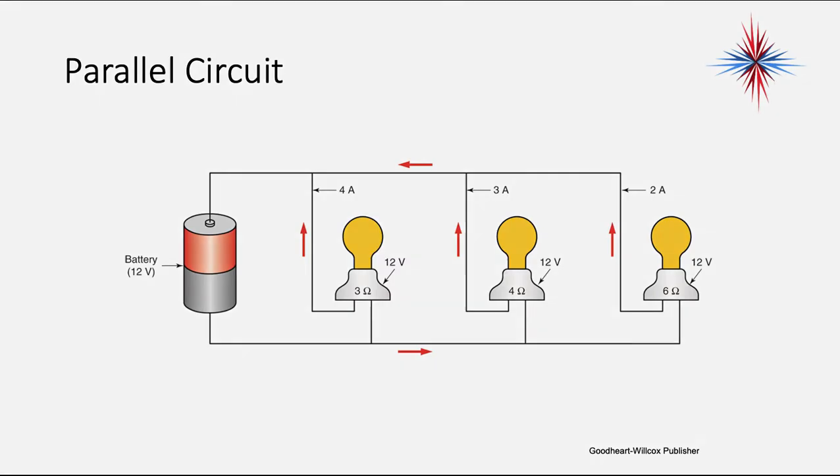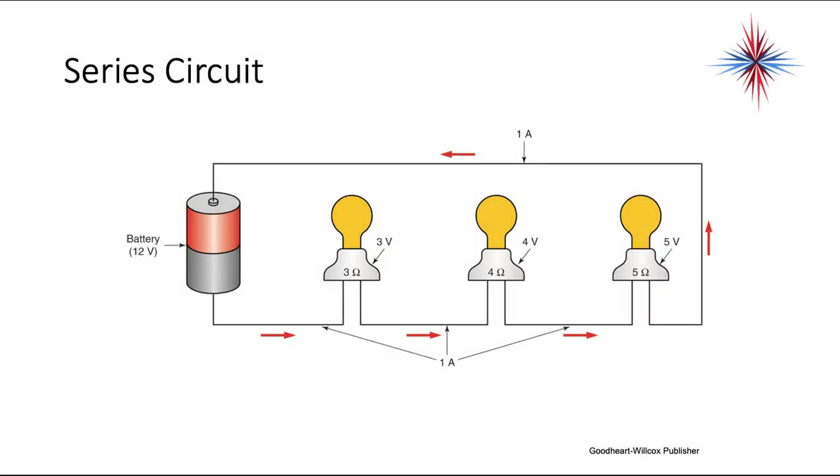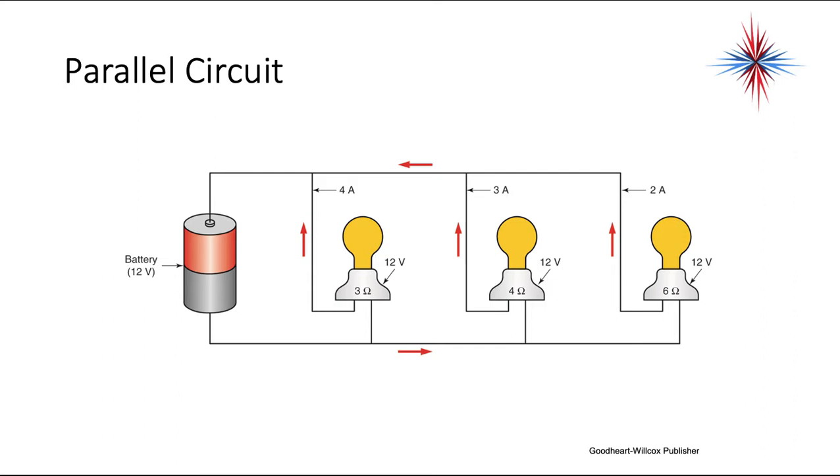In the HVAC industry, series circuits are used for safeties for the most part. Safety controls are all wired in series. If any safety control opens, we want the circuit to cease to operate. Parallel circuits are most often used for the load side of the system, the part that does the work, because we want every load, which would be motor, heater, everything else, to get full source voltage.